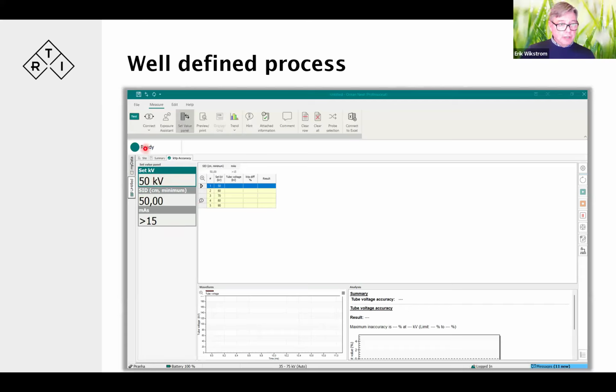Okay, we're good to go. We have a ready signal, a green light, and we collect the data. After the first exposure, we have read the data from a probe which is in the field. It gives us here 49.22. The software will calculate the difference in percentage and give us a result of pass or fail, based on the analysis that we have down here.